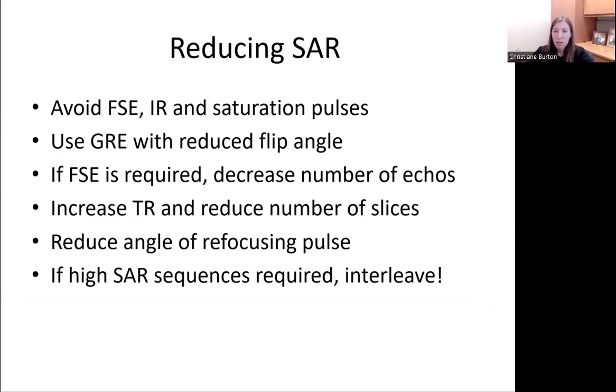In a previous slide, I talked about what SAR is proportional to. So things like tissue conductivity, patient body size, field strength, RF flip angle, and duty cycle. Considering these factors leads to a better understanding of what sequences produce the highest levels of SAR and can help provide a wide range of potential strategies for reducing it. Since SAR is proportional to the square of the flip angle, sequences with the highest SAR levels tend to be those containing a large number of 180-degree refocusing pulses applied over a short period of time. Fast spin echo is the archetype, followed by the inversion recovery family. Saturation pulses of all types, fat sat, spatial sat, and especially magnetization transfer may cause SAR limits to be exceeded.